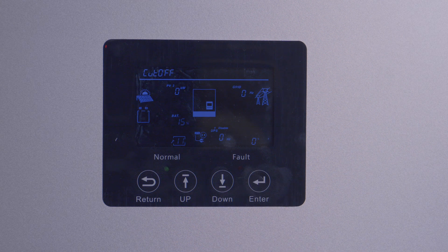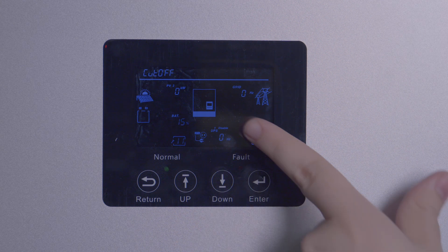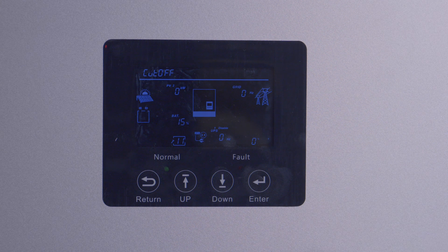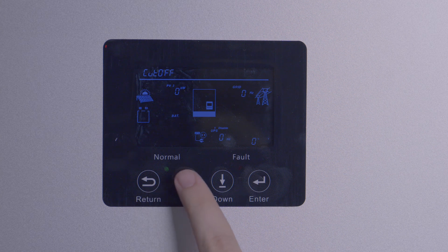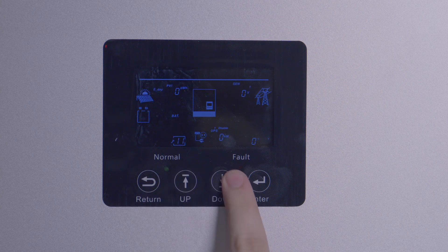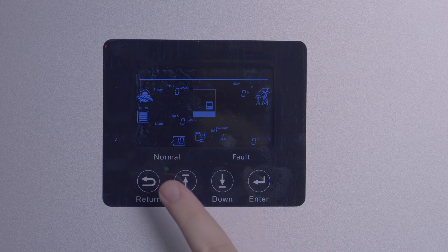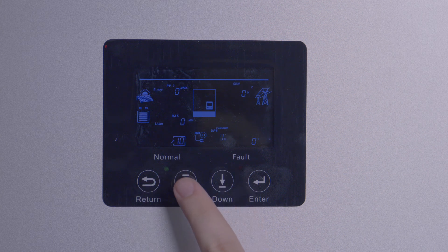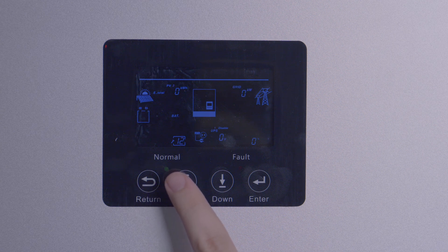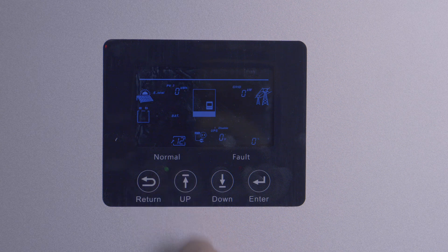If the grid goes down, it will switch back to battery or generator. Setting twelve, while seemingly similar to eleven, is for total battery cutoff. This is the point at which the battery will stop being discharged even if the grid and/or generator are not present.